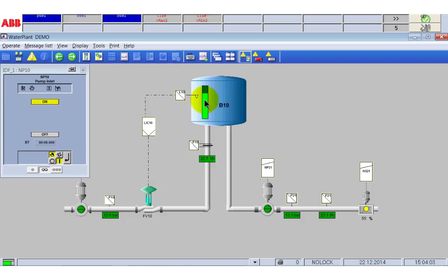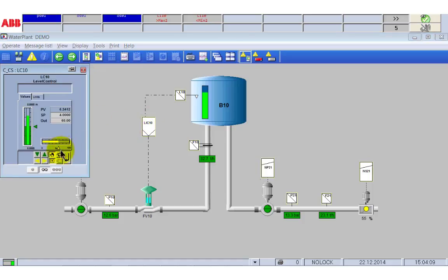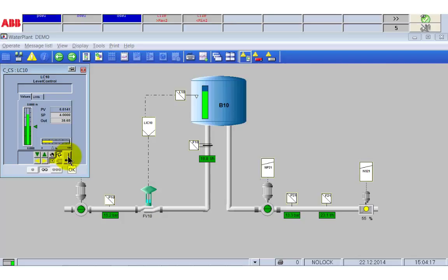To avoid this we start the control loop. Open the face plate and switch to automatic. You see that it reduces the out value for the positioner immediately which will close the valve. As the set point for the level is 4 meters this level will be reached after a while.